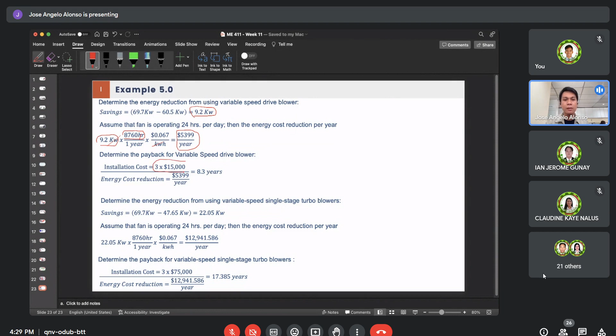Kailan naman natin mabe-break even o magkakaroon ng payback, mababawi yung capital na ginastos natin pag nag-install tayo ng VFD? So divide natin ang installation cost na 3 times $15,000, kasi tatlo yung blower, tatlo yung motor, tatlo yung i-install nating VFD, divided by the energy cost reduction of 5,400 per year. So magiging 8.3 years. Within that span, diyan pa lang natin nababawi yung nagastos natin sa installation ng VFD. After 8.3 years, maganda na yung balita kasi doon na tayo nagsisimulang makatipid in terms of power and cost.